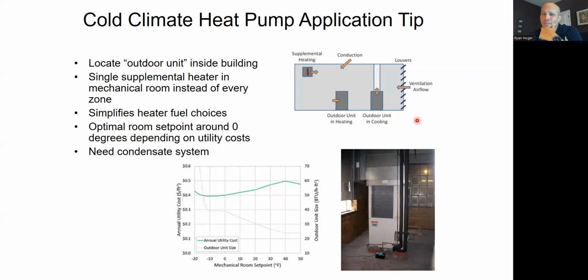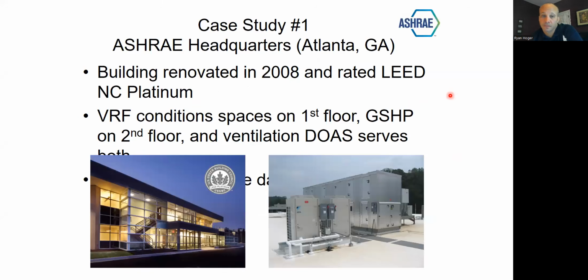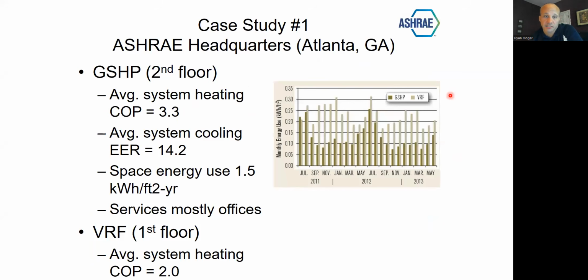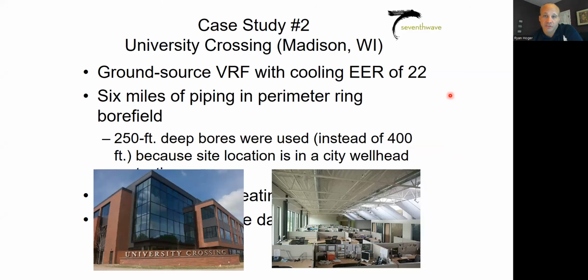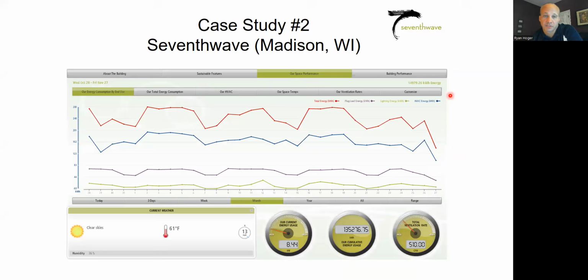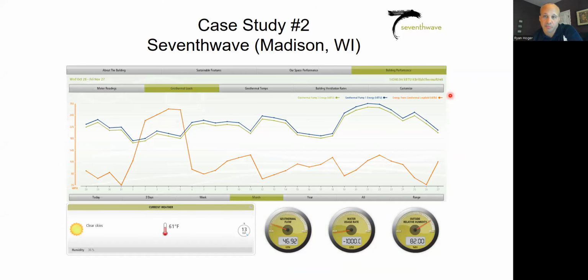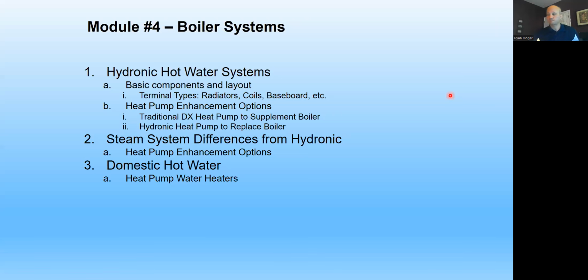And you're like, dude, why am I going to heat this room instead of just heating the zones I care about? Well, the reason is now I have to pull one electrical feed or one gas line to heat that room versus pulling electrical feed to 33 zones, right? So it's a lot less on the installation cost. Not a great idea for every job, but there are jobs where this might help you out. All right. And then the last thing on here was a couple case studies. I'm going to leave them on there so you guys have those notes from a couple different buildings. But it doesn't really directly apply to our moment right now.